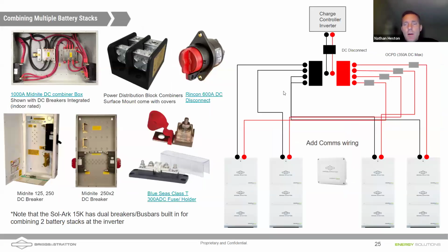If you're doing multiple inverter systems, or if you're doing more than 2 stacks of batteries, you're going to need some type of battery combiner. So there's an example I'll show in a little bit of a system with 4 stacks of batteries, right? And that utilizes the Midnite 1000 amp combiner on the left side of the screen.